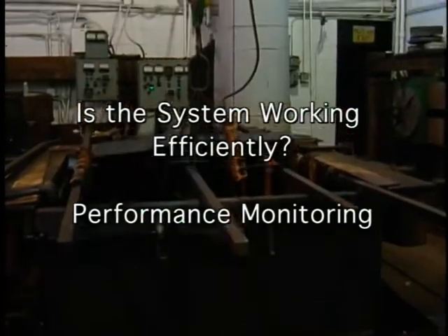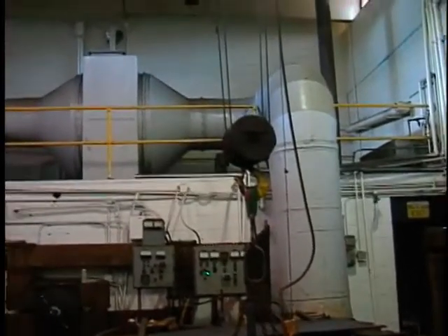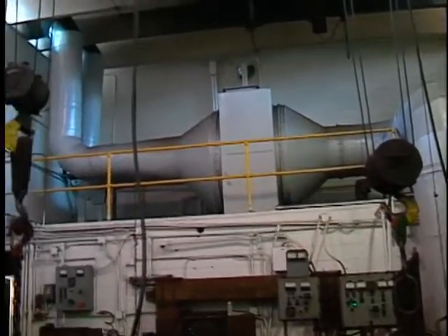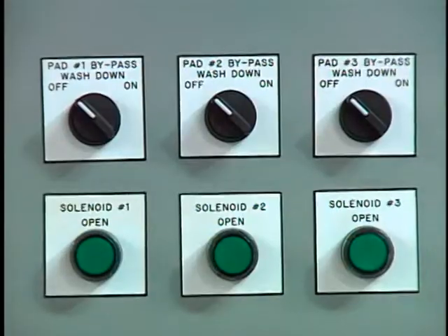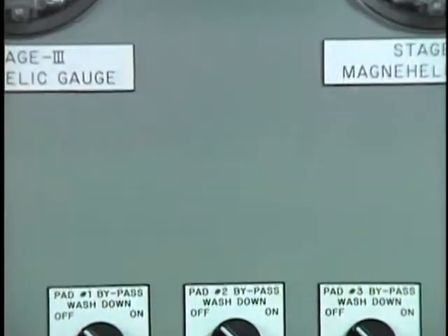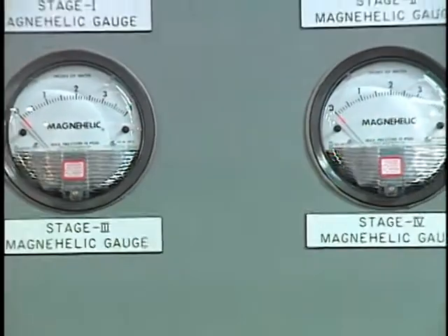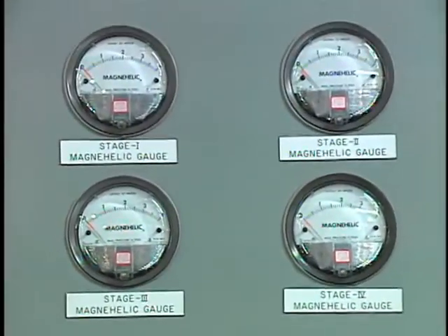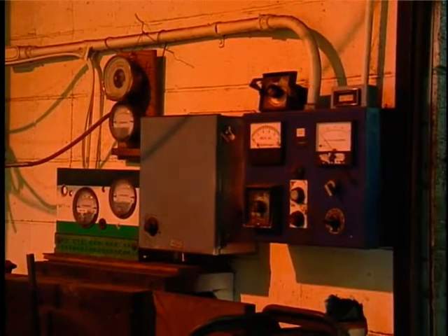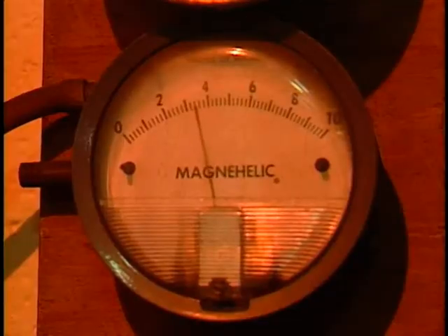The ability to evaluate potential problems during a field inspection will depend on how well the system is instrumented. Most large systems are well instrumented. However, smaller systems may have limited instrumentation. Performance evaluation of these systems will be difficult unless measurements of important parameters are made.